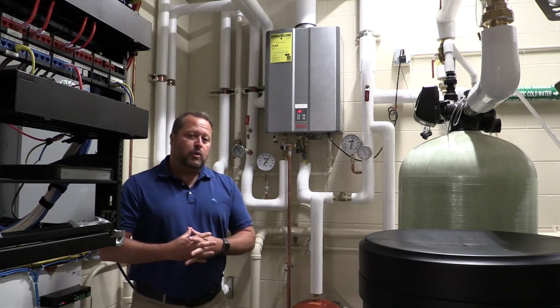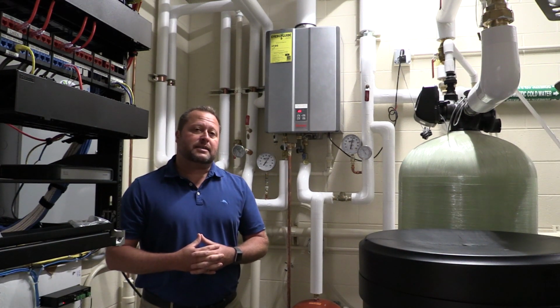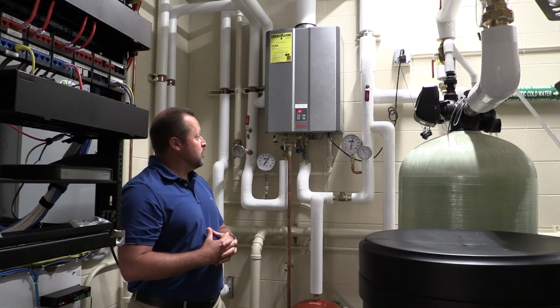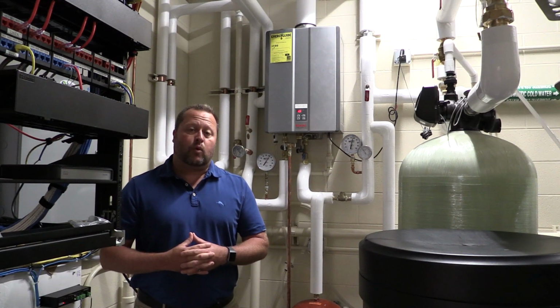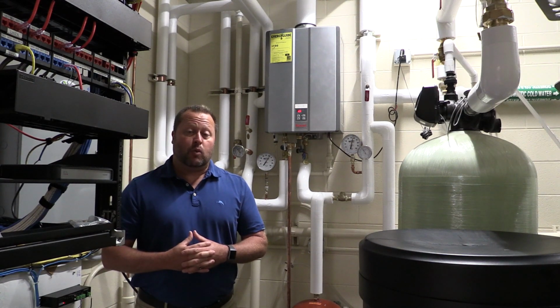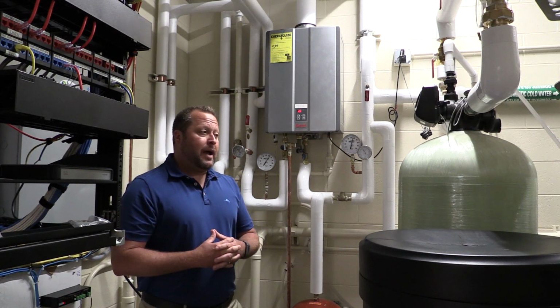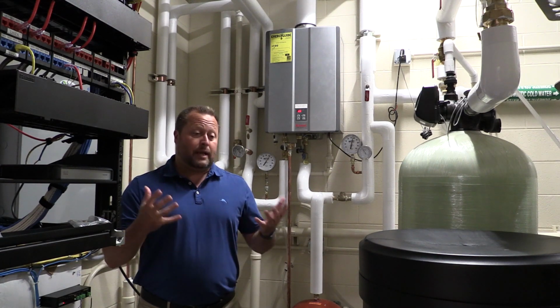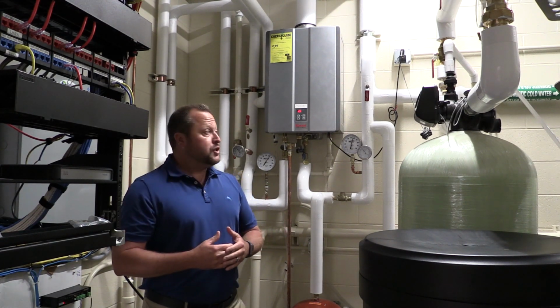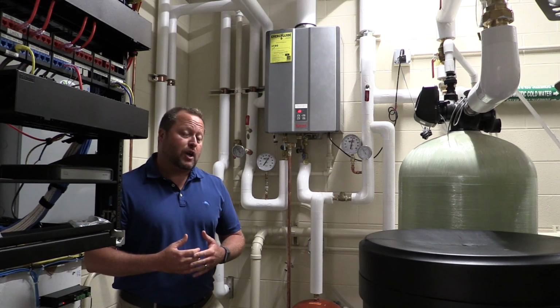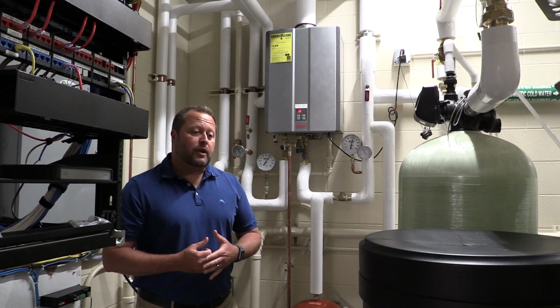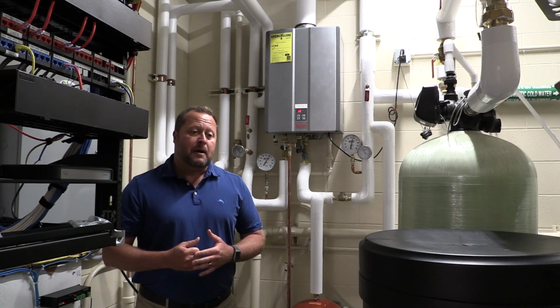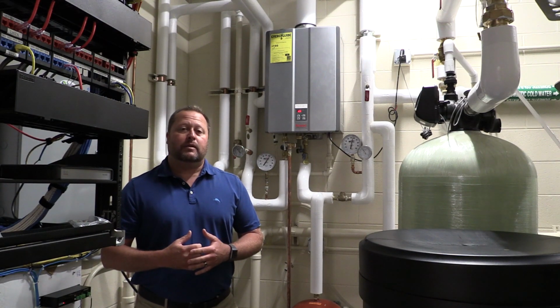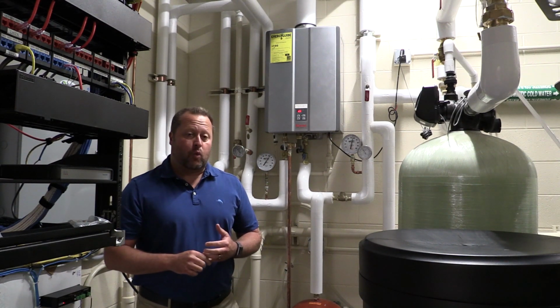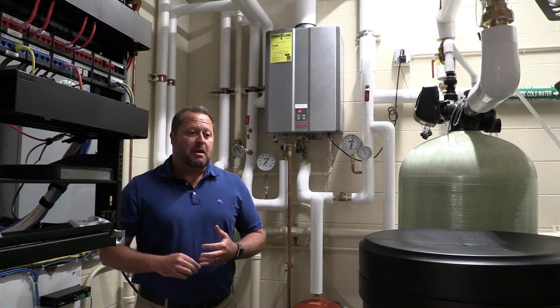If there is a problem with the tankless water heater, it does have a self-diagnostic system, and it'll throw a fault code up on the screen, giving the contractor or the maintenance person indication as to what is going on with the system. Rinnai provides tankless water heat indefinitely. So this unit fires at 199,000 BTUs and can do roughly, with a 70-degree delta T, about 5.5 gallons a minute. And it will provide hot water indefinitely.